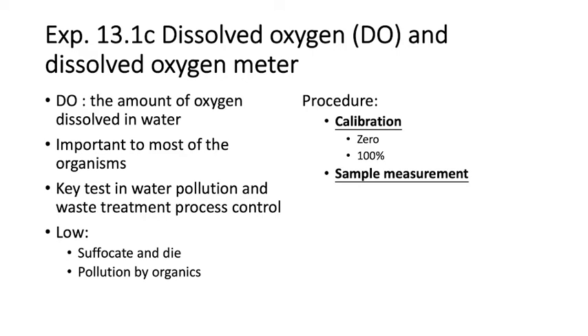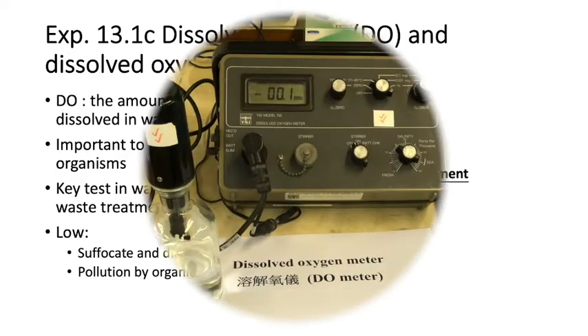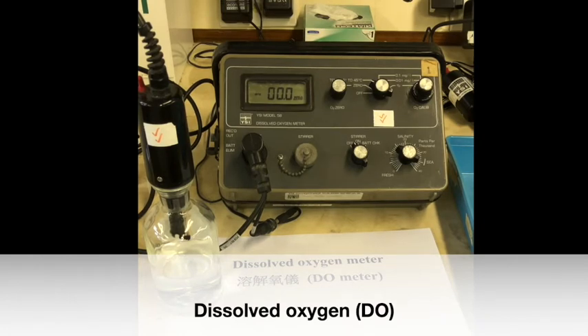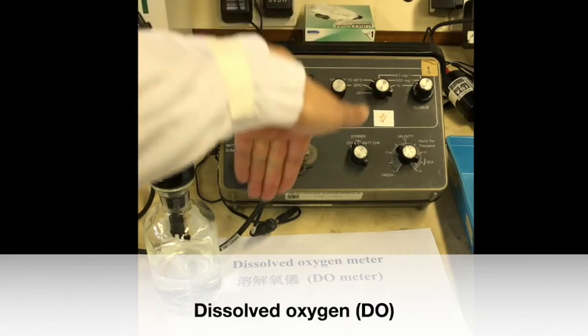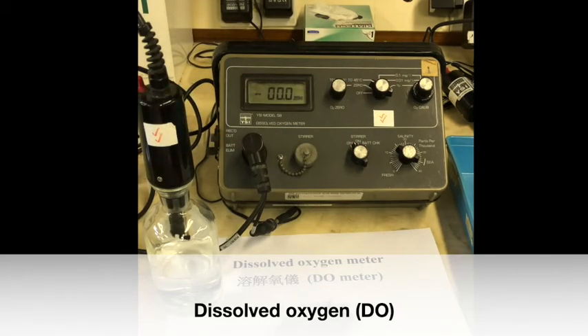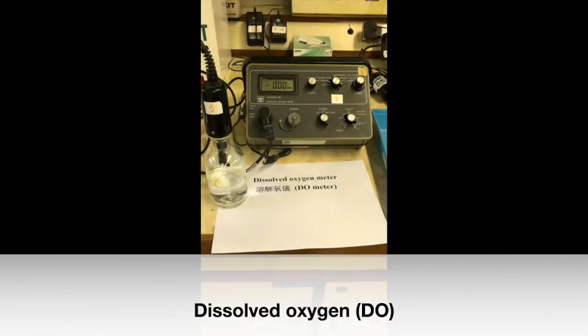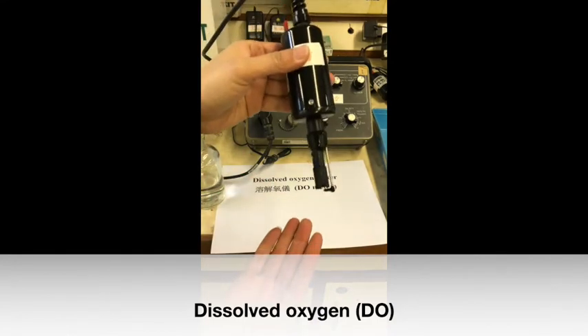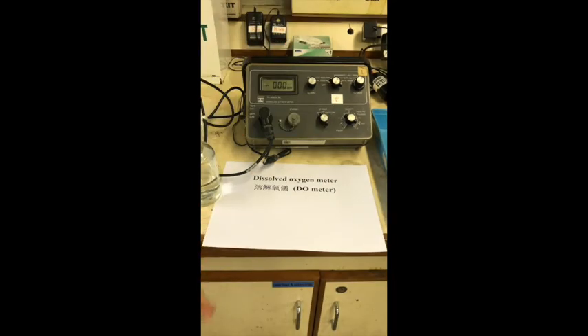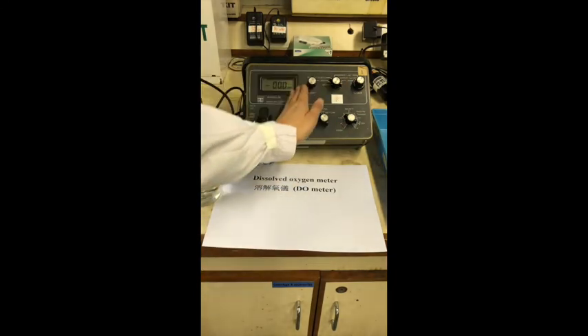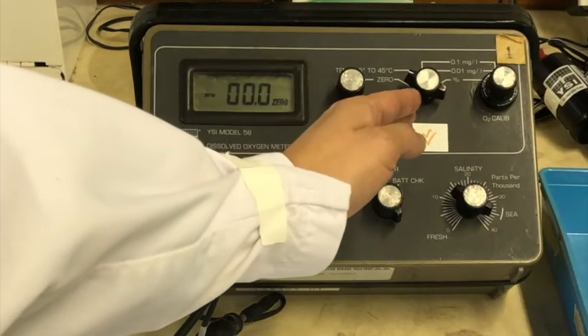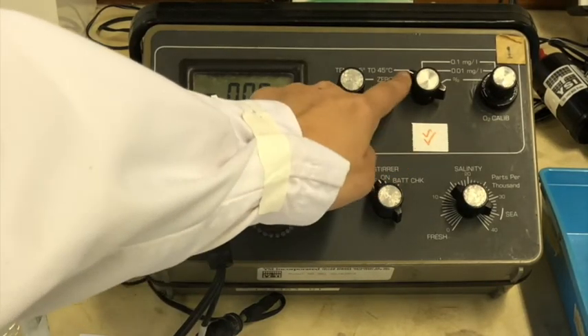Dissolved oxygen is measured by a dissolved oxygen meter. There are two steps for using a dissolved oxygen meter, which include the calibration and the measurement. Let's start the dissolved oxygen measurement. This is a dissolved oxygen meter for measuring the dissolved oxygen. This is the control panel for the dissolved oxygen meter, and this is the electrode for dissolved oxygen measurement. I will introduce the buttons on the control panel. This is the function switch, and this is the pointer.